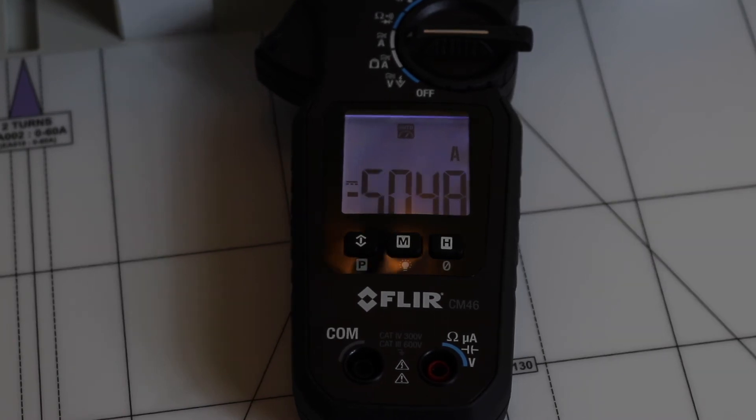and you can see it's positive polarity. What I'll just do is stop the test set. I'm going to swap over the leads and hit the go button again. Now this should be negative. There you can see I've got 50.4 or 50.5 amps, and that's showing a minus now because I've reversed the connections coming out of the Seaward.